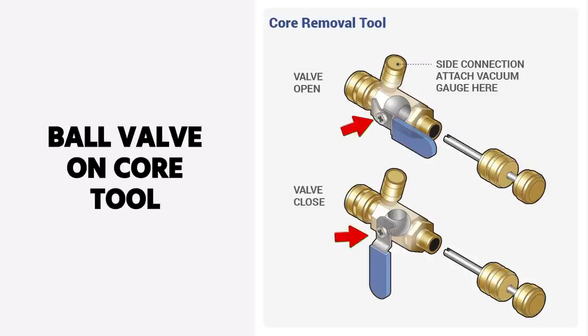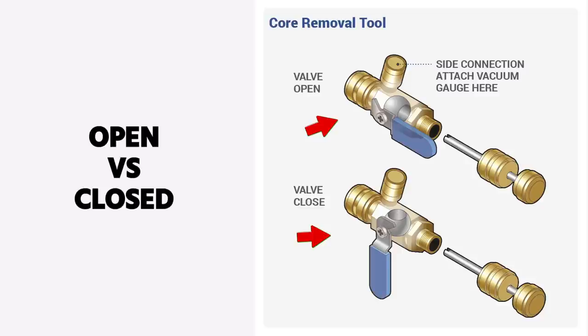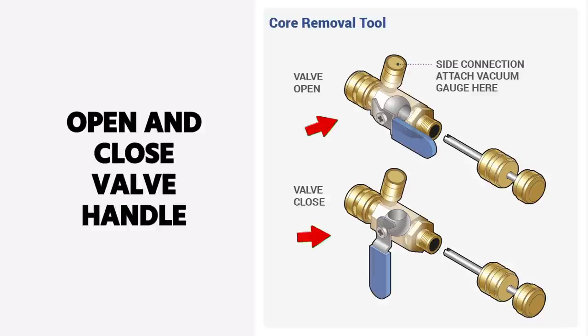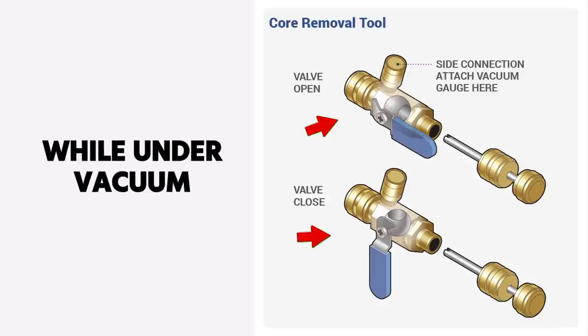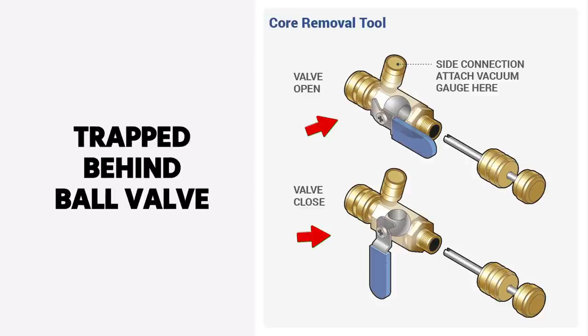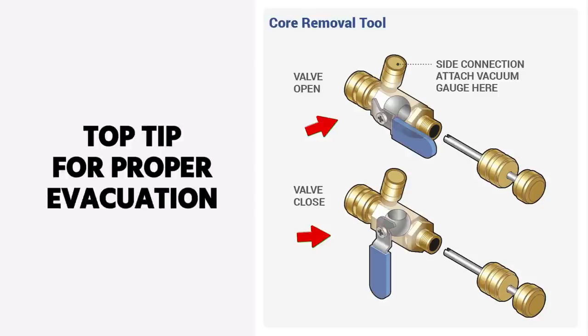You have to understand the ball valve on your core tool, make sure to understand open versus closed. Another thing that's a good idea is when you are under vacuum with any core tool, exercise the valve. Open and close the valve handle while you are under vacuum, and that will allow any air bubbles that are trapped behind the ball valve to get evacuated as well. That's just a good top tip for proper evacuation.